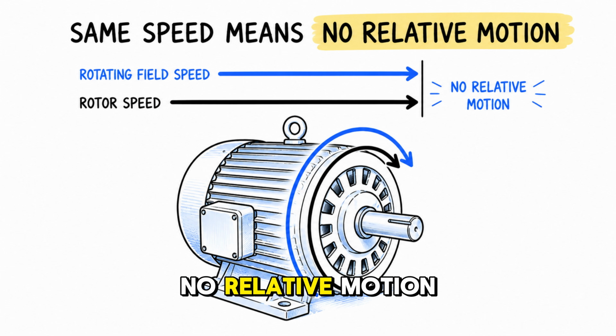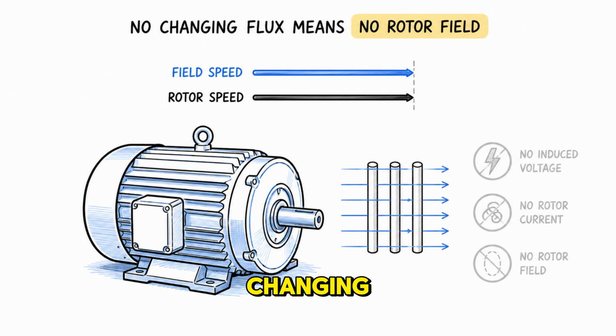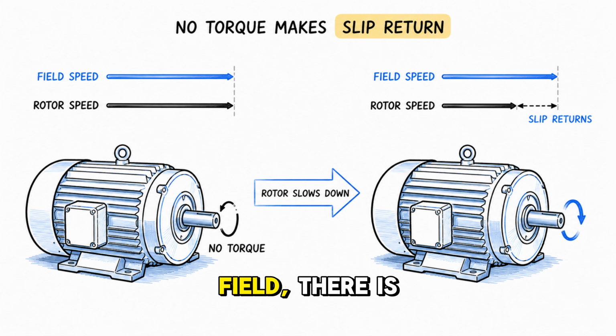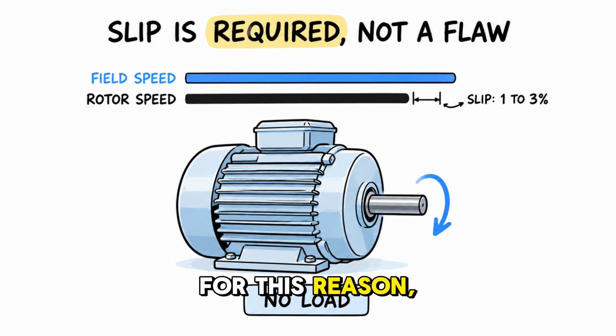There would be no relative motion at all. That means no changing flux through the rotor conductors. It means no induced voltage, no rotor current, and no rotor magnetic field. With no magnetic field, there is no torque. The motor would immediately slow down, and slip would reappear. For this reason, slip is not a design flaw. It is a fundamental requirement for the motor to operate.